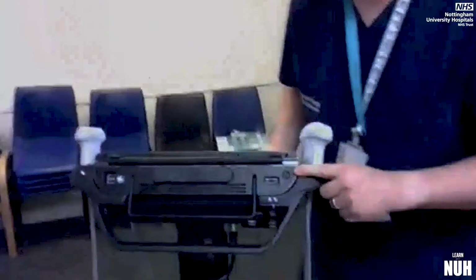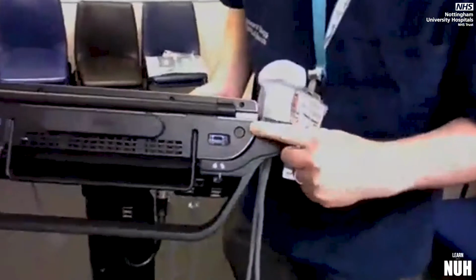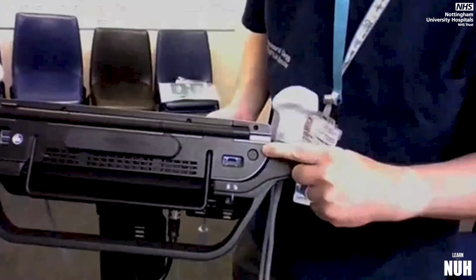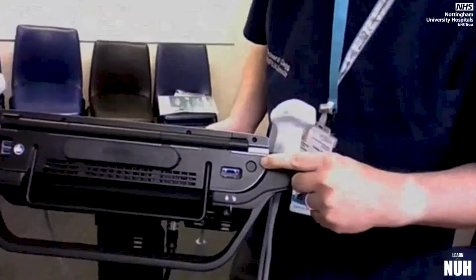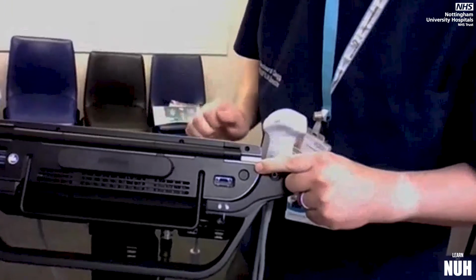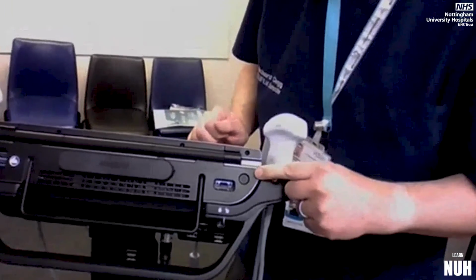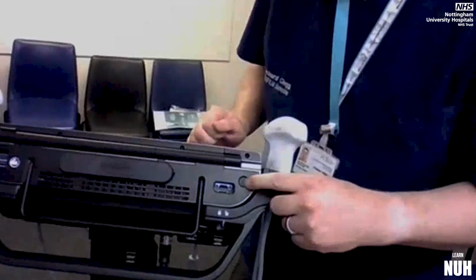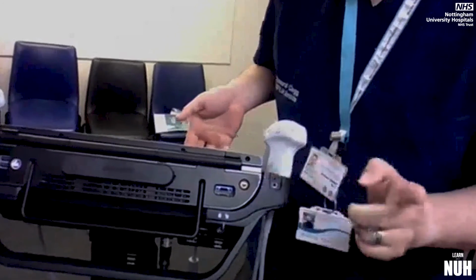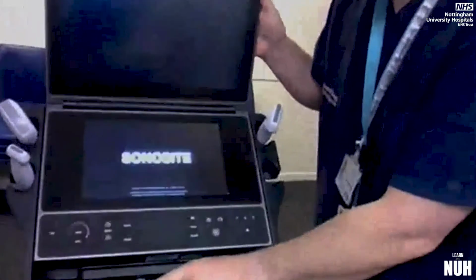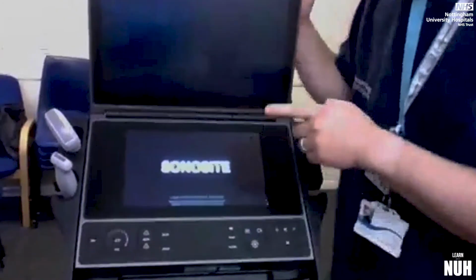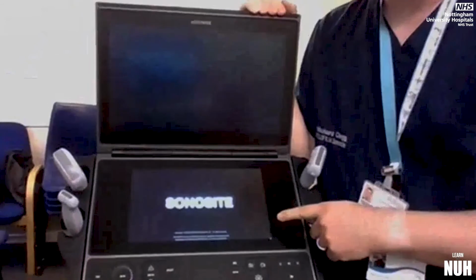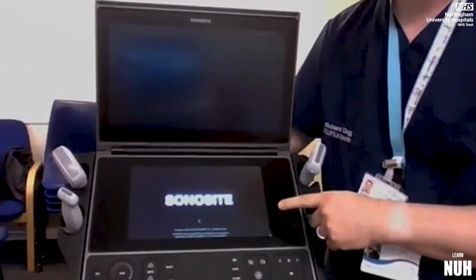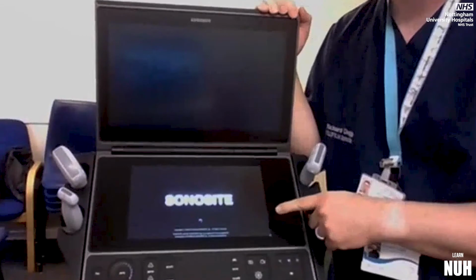The power button is round the back, so that's on purpose so that you don't switch it off accidentally mid-procedure, or if you're asking an ODP to press buttons for you. The ancient systems, the power button was near the new patient button, which was a bit annoying. Boot up sequence, so if you press it, it's just a 1-click and press, and it's a 45-second boot up time compared to the older systems that were 25 seconds, so it is a little bit longer. You get an initial screen. The screen will drop off after a short time. Don't start pressing the power button repeatedly because all you'll do is switch it back off again.